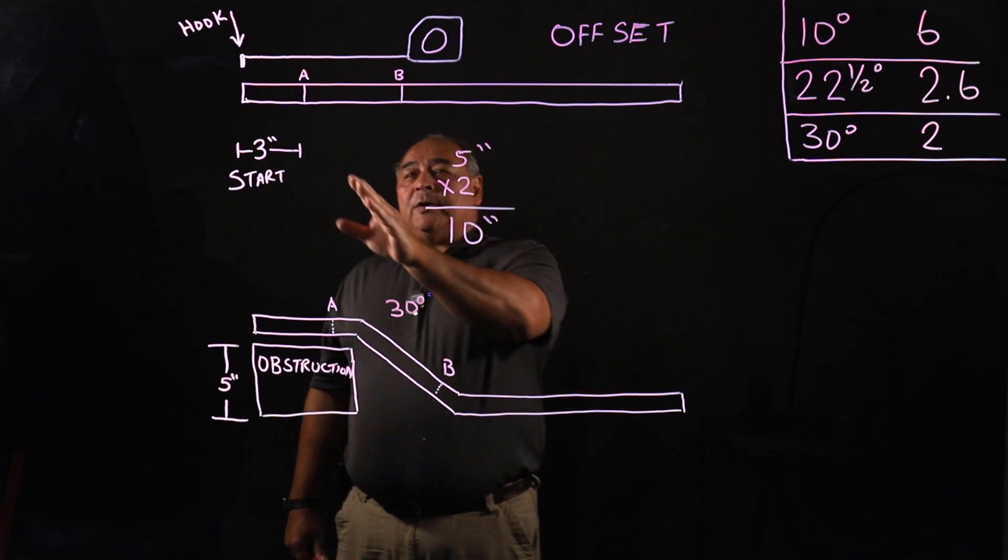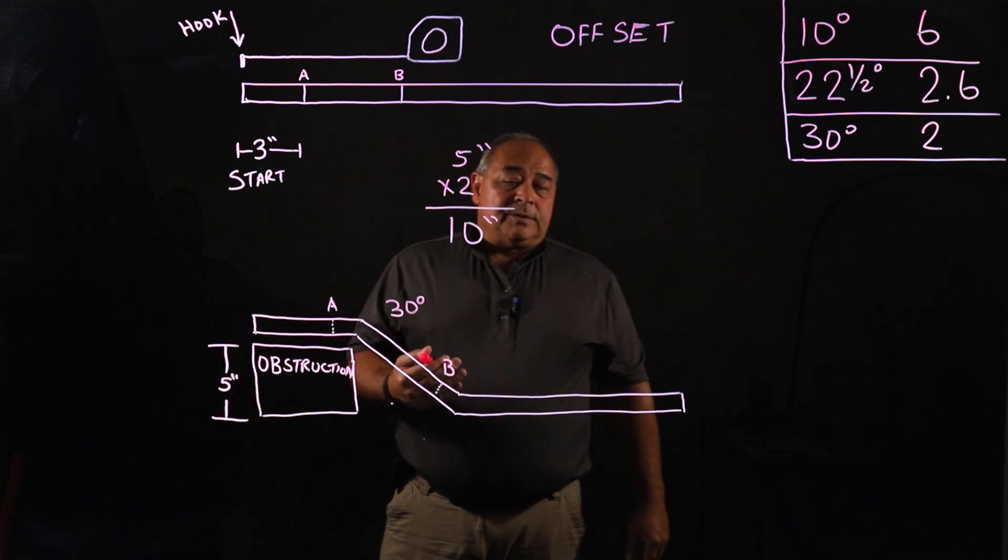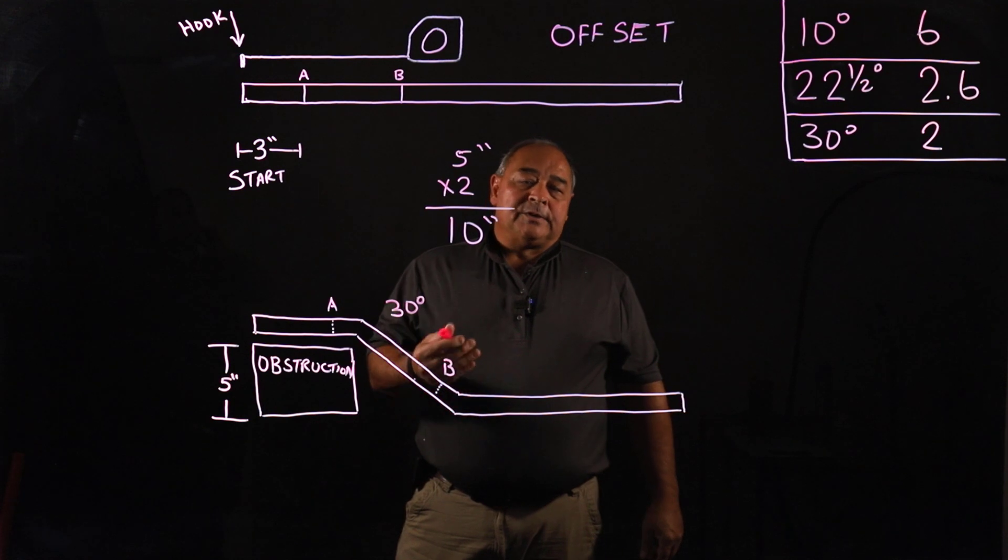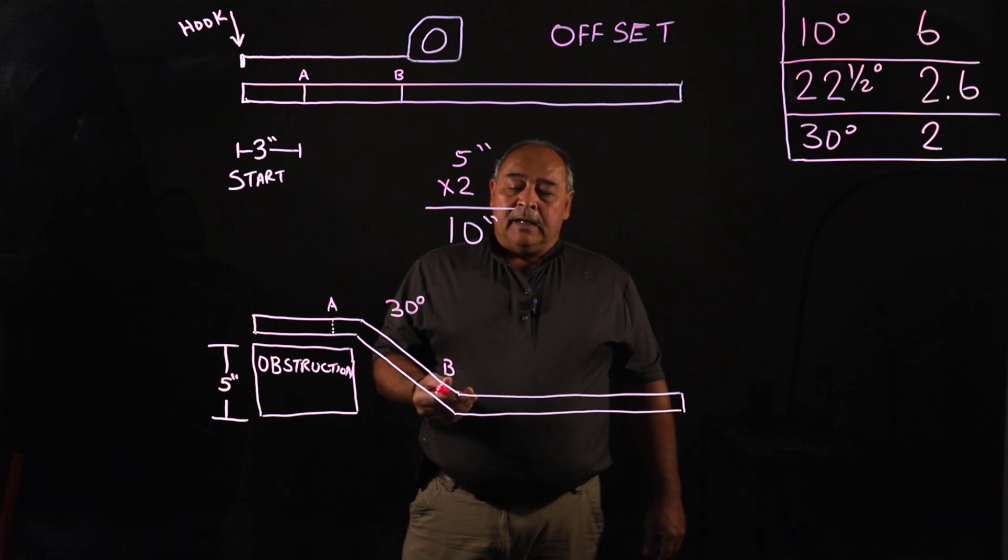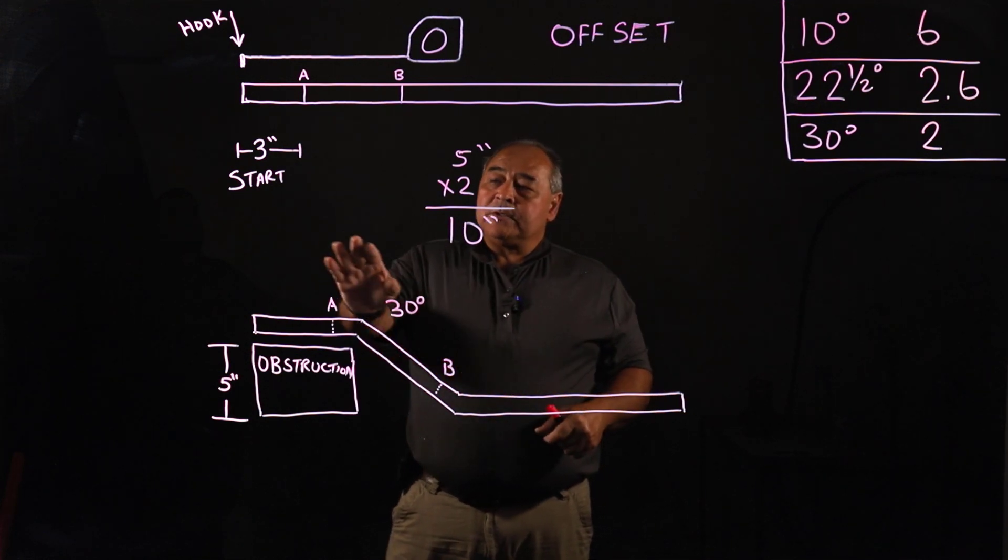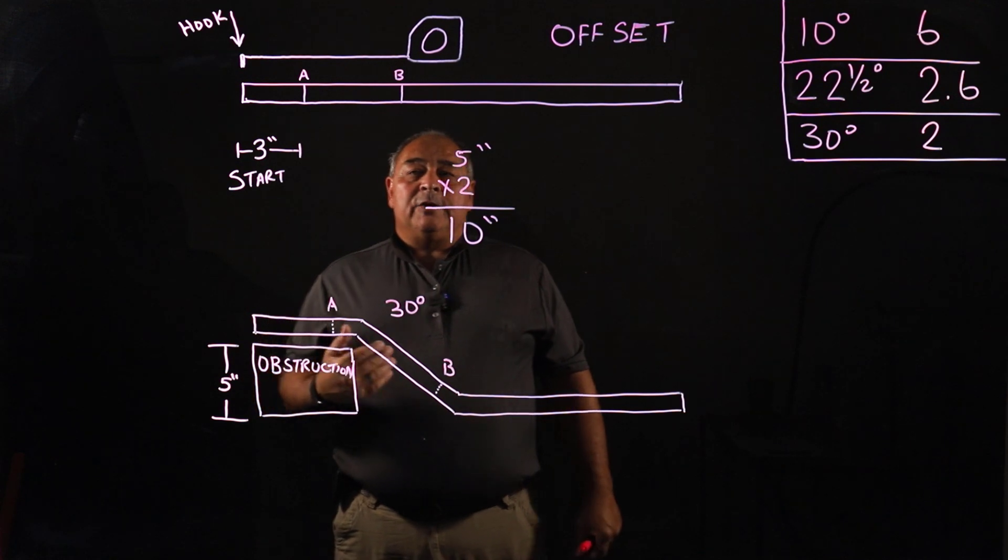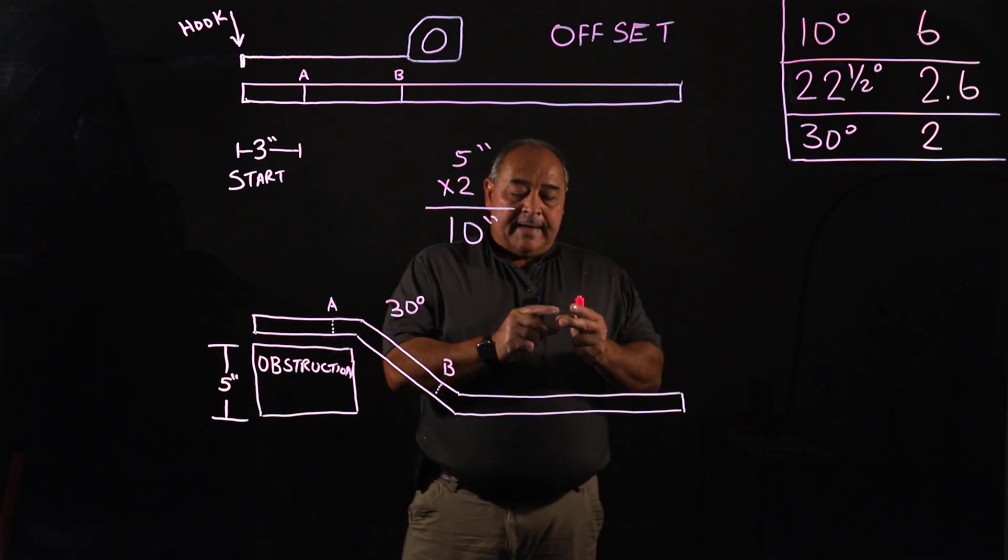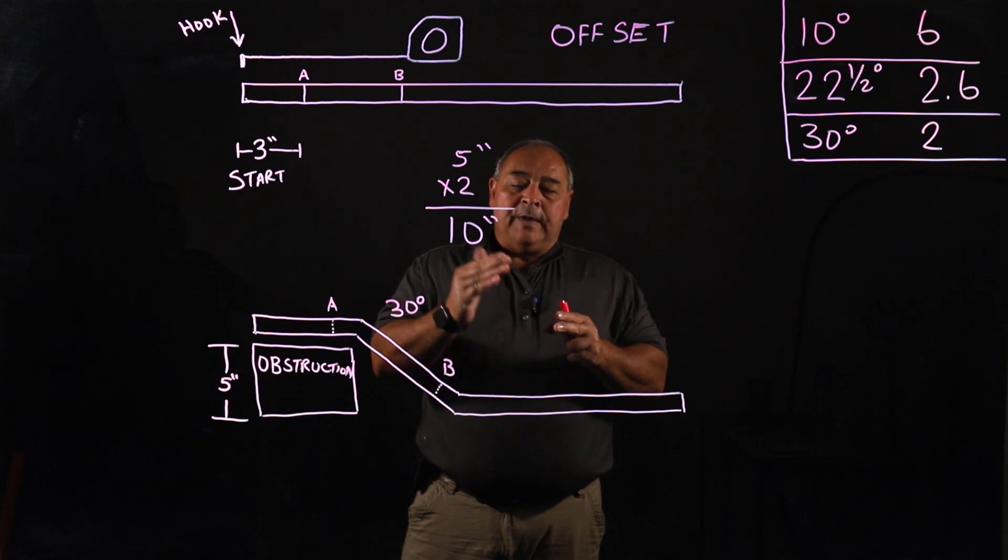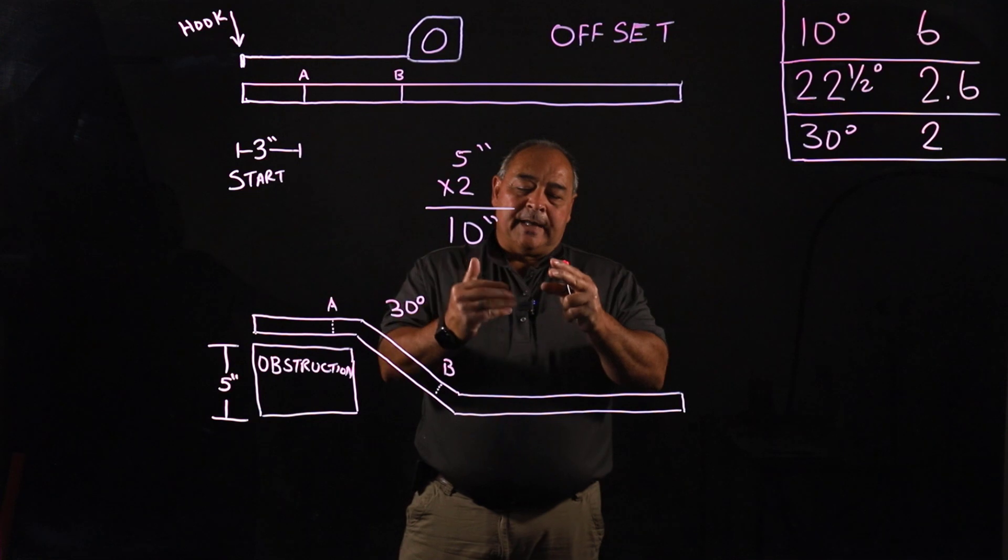Now where do you start? You're going to have an A and B mark and this is up for, again, suggestion. Some people will say different than what I'm going to suggest, and some people will have a reason to start at a different place. I'm going to suggest that we start at three inches from the end of the pipe. The reason why is the bender itself has some meat between where the angle starts and where the bend hook actually connects.